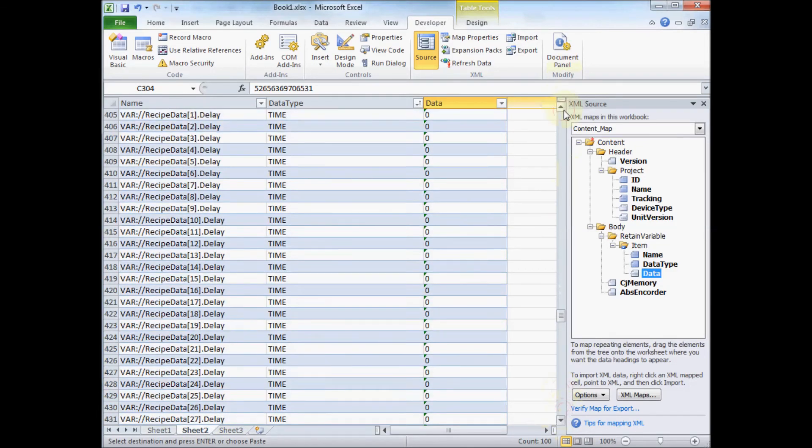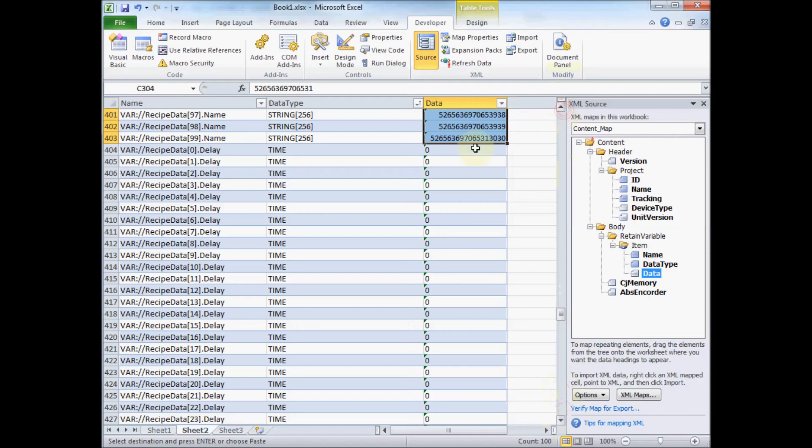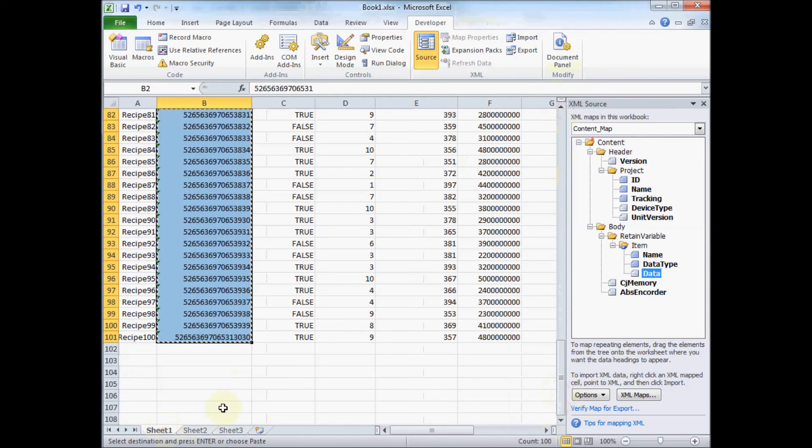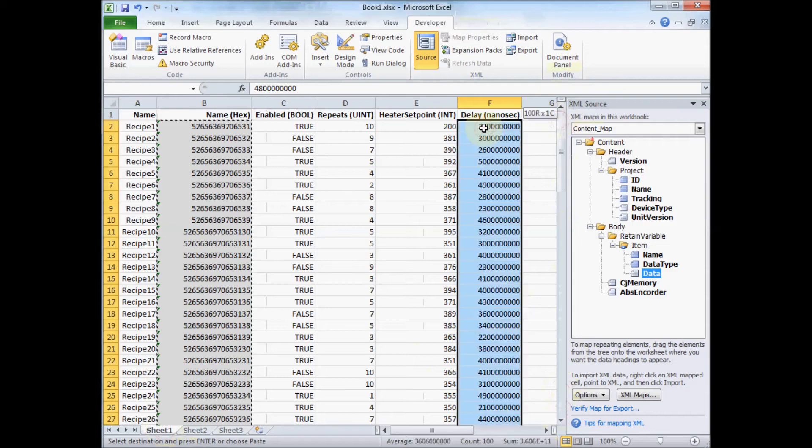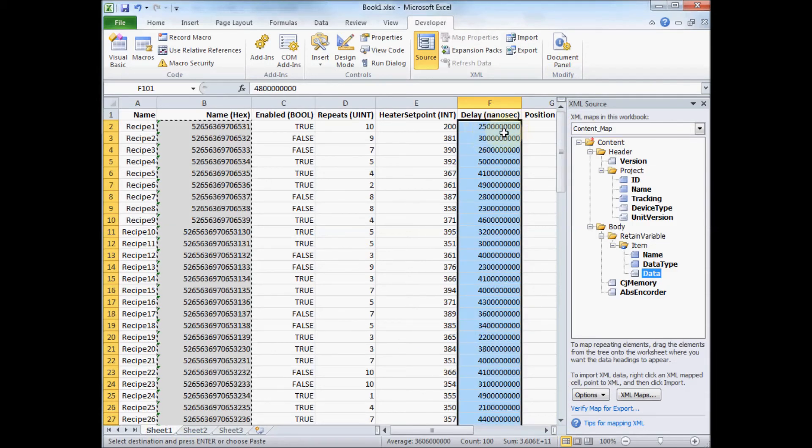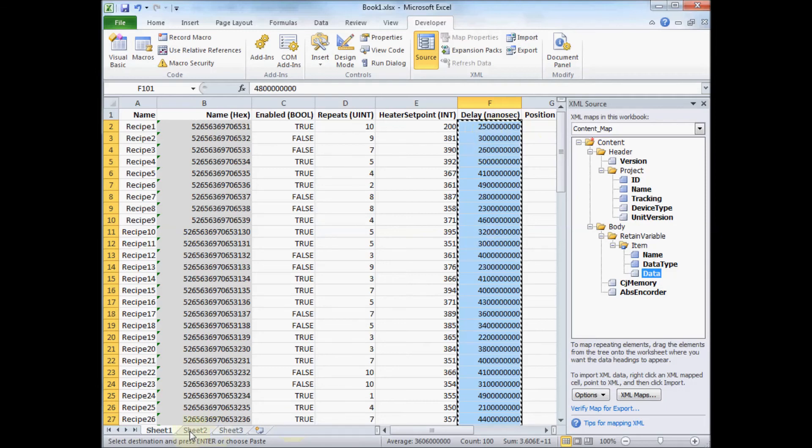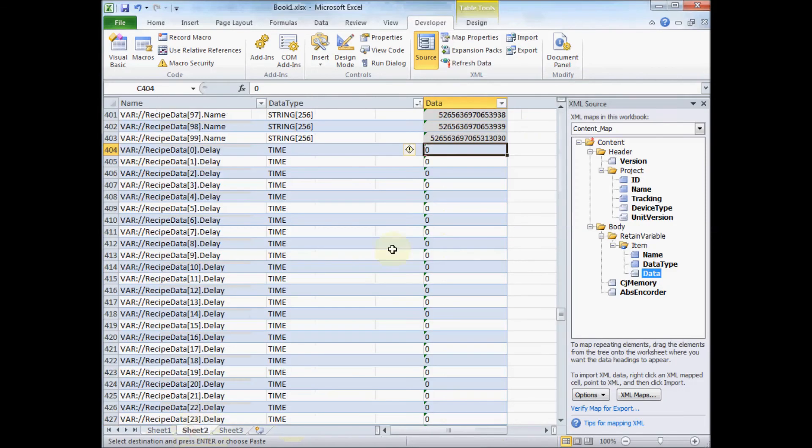Time. Time is stored in nanoseconds in the PLC. So here's my times here. So this very top column, two five and then eight zeros, that's actually 2.5 seconds is what that represents.